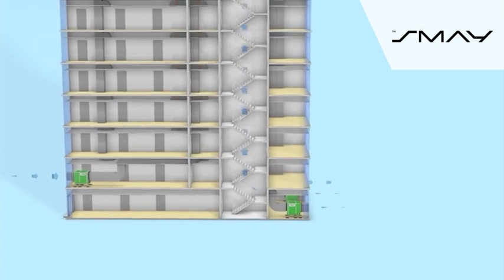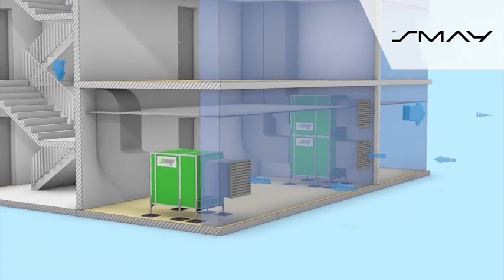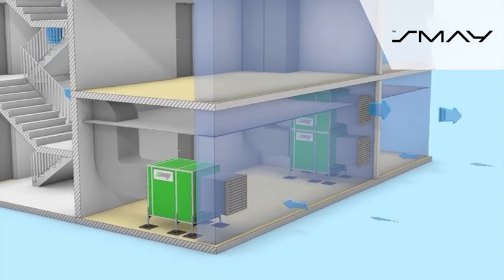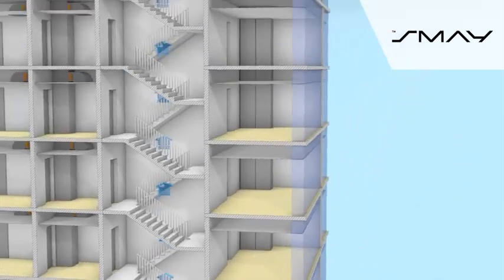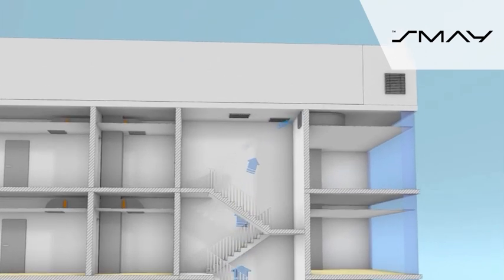Locating all units in the lower floors of the building is optimal since it significantly reduces the risk of sucking smoke from outside. However, if this is not possible, it is allowed to install the units on the roof, but in such case it is recommended to provide a twin air intake system.